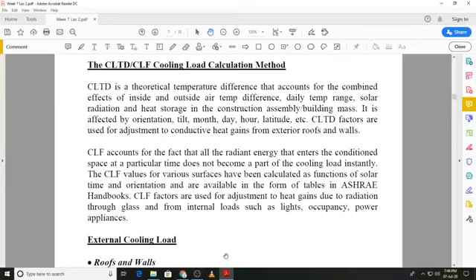Then we have the cooling load factor. The cooling load factor accounts for the fact that the radiation that enters the conditioned space, it may be the solar radiation that is entering through transparent surfaces, or it may be the thermal radiation that is emitted by any source inside the conditioned space: lights, occupancy, or appliances.